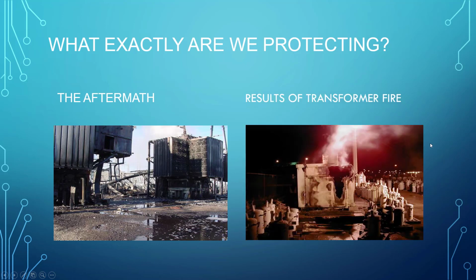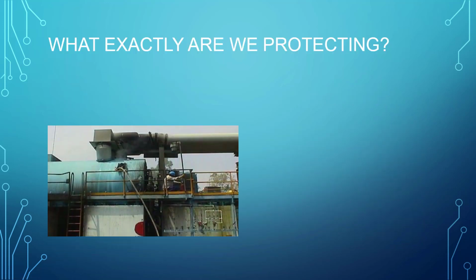What exactly are we protecting in an electrical system? We are protecting against generator faults, because a generator is a key component of our electrical system. That's the main component that is pumping power into the system. So if you have an issue with your generator, everything is affected. Your transmission line becomes useless, because your generator, which is supplying power to the transmission line, is not doing it efficiently anymore. So your transmission line just becomes an empty vessel.